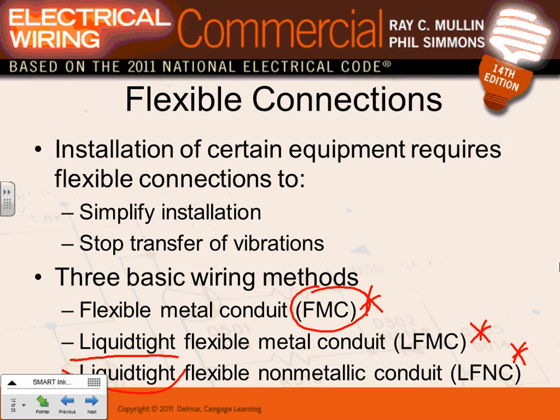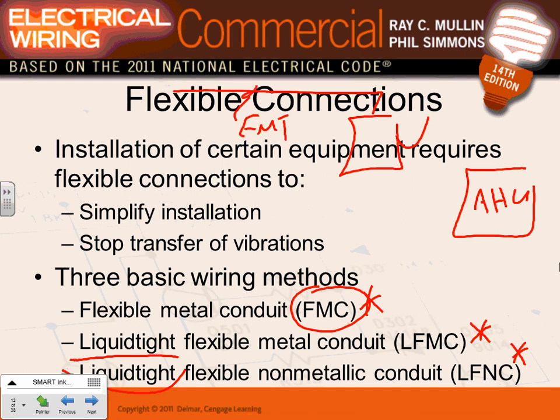Highly corrosive environments are typically underground with chemicals eating into metal, or in chemical plants where chemical vapors eat into steel. For those environments, liquid-tight flexible non-metallic conduit is your conduit of choice. The typical installation: here's your air handling unit, you bring your EMT conduit to a disconnect, and from the disconnect you flex it into the air handling unit. If it's outside - which most rooftop units are - use liquid-tight flexible metallic conduit, just like the outside unit of your air conditioning.